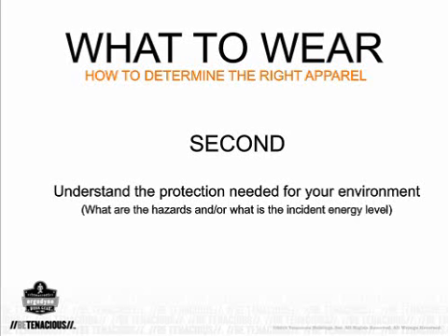If you cannot find something, you can always layer up. You may need to layer up to reach a specific CAL rating for your hazard. When layering garments, know that you cannot simply add up the CAL ratings, but rather you need to test the garments together to obtain an accurate CAL rating for the combination. Air gaps between two garments can impact the overall CAL rating, which is why testing two garments together is necessary.